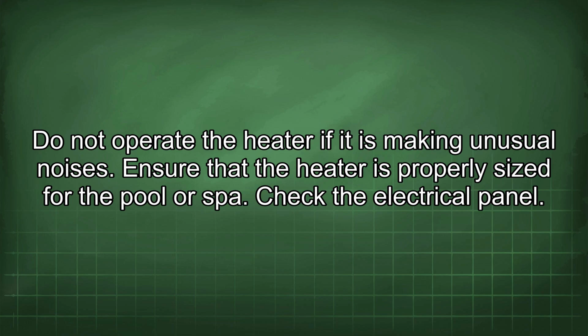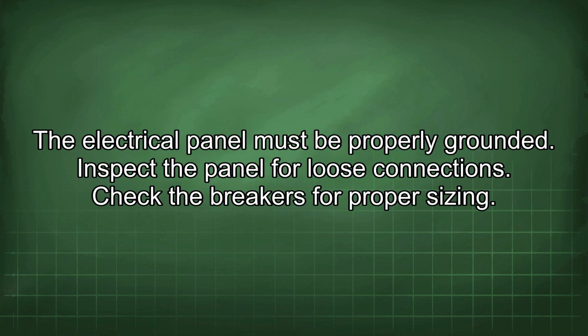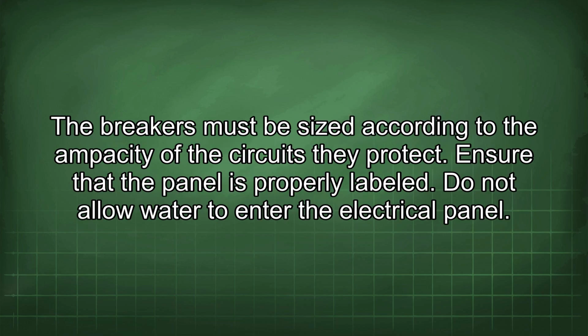Check the electrical panel. The electrical panel must be properly grounded. Inspect the panel for loose connections. Check the breakers for proper sizing. The breakers must be sized according to the ampacity of the circuits they protect. Ensure that the panel is properly labeled. Do not allow water to enter the electrical panel.